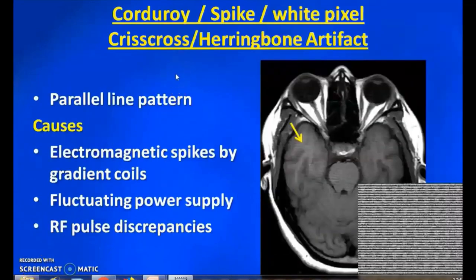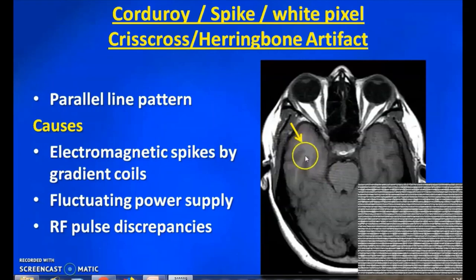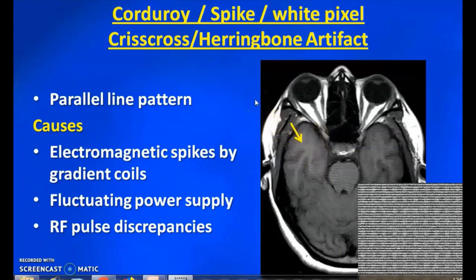Corduroy artifacts are spike artifacts appearing as parallel lines inside the anatomical part. These are mainly caused by electromagnetic spikes from the gradient coils and switching power supplies. Sometimes faulty coils also cause this type of artifact.